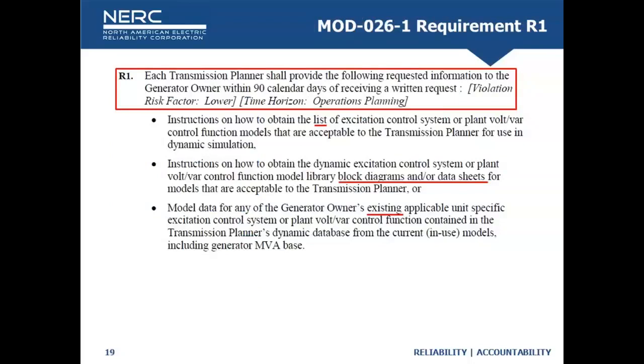Requirement 1 is that each transmission planner provides the requested information to the GO upon request, and those three bullets there list acceptable models. So the TP should be ready to give a list of acceptable models. When the transmission planner comes to me, for example, and says they're getting models and they're not using the right models, I just point to R1, bullet 1, and say well you obviously didn't provide them with a list of acceptable models. They're required to use a model that's deemed acceptable by the transmission planner, if that information is provided. Number 2 is the block diagrams and data sheets, and number 3 is the applicable GOs, existing equipment providing the models for the other resources if needed. So essentially the TP is providing the data needed to be able to provide back verified models in the right format, the right level of detail, etc.